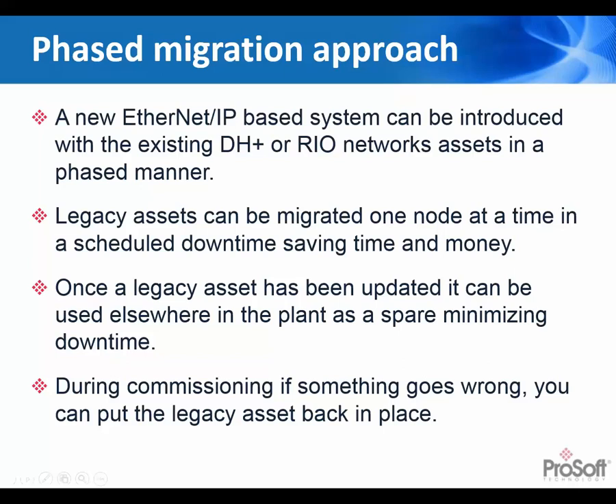So what this means for the controls engineer is that they can be more reactive. They can replace equipment as it breaks. They can be more proactive. They can replace legacy equipment as it fits in with a maintenance budget, and they can manage spares more effectively. And it's a relatively quick option to keep the plant up and running in the event of an emergency. Also, the controller code may not have been documented as well as it should have been, and the person who did it may have left the plant, so it may be an option to leave the controller alone as much as possible.